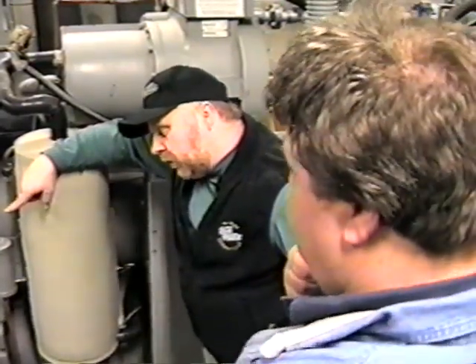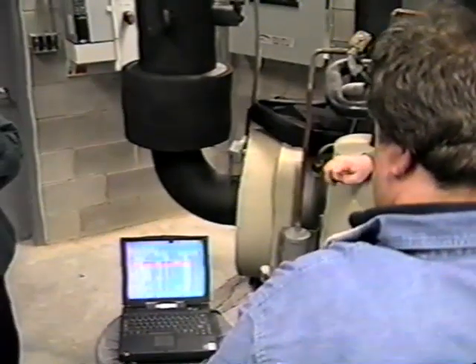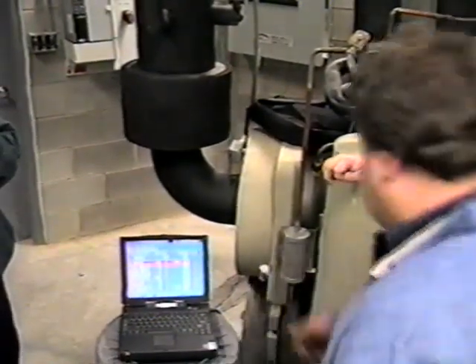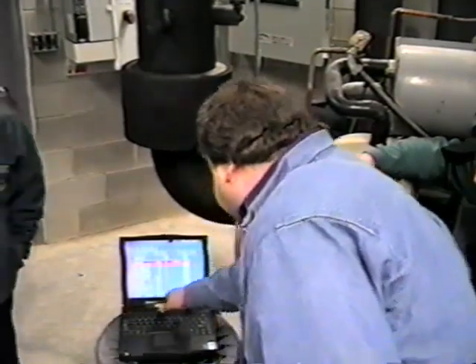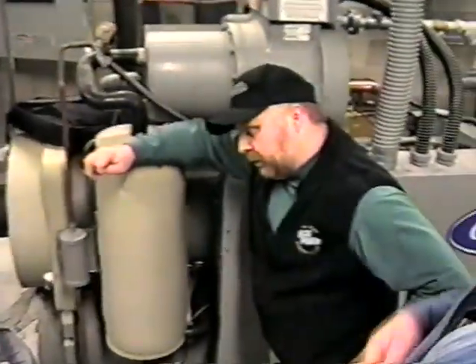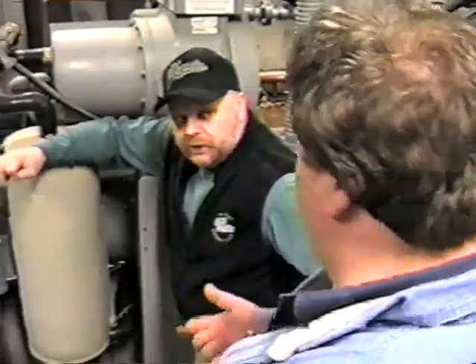Is that the cooling tower sump temperature? That's the one that should be at about 70? Right. Okay. And then the other you're going to see is this tower bypass valve. Right. Is the actual one that will help govern that temperature.